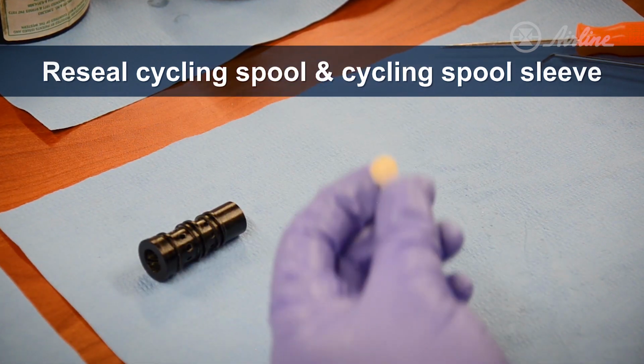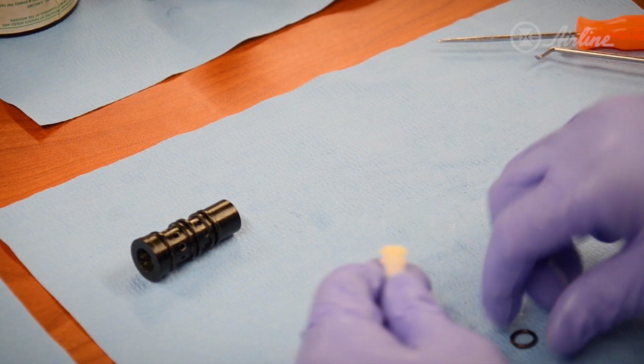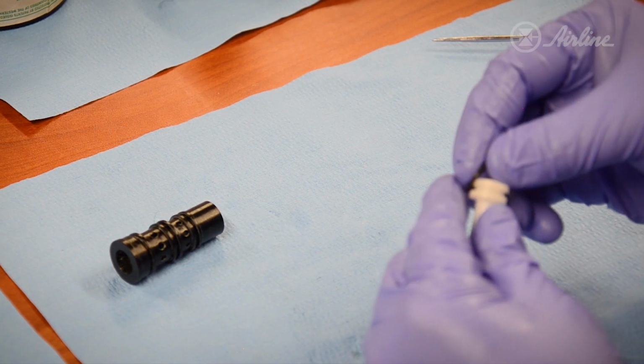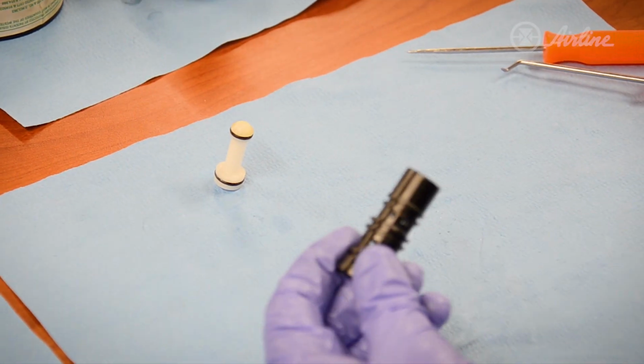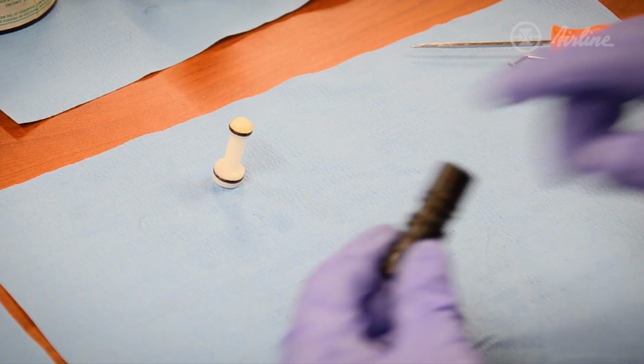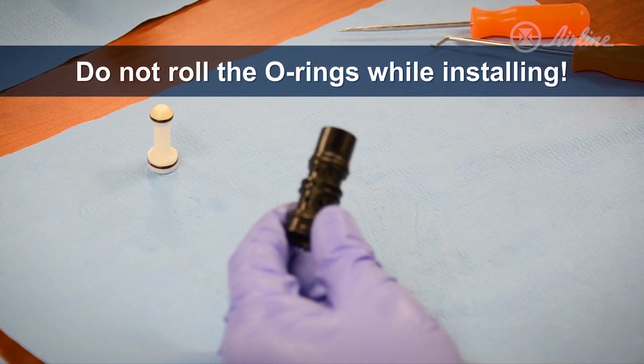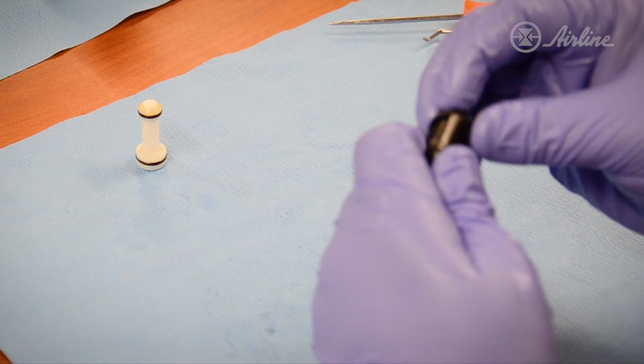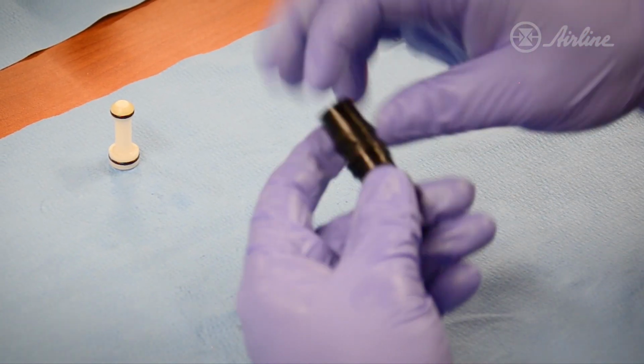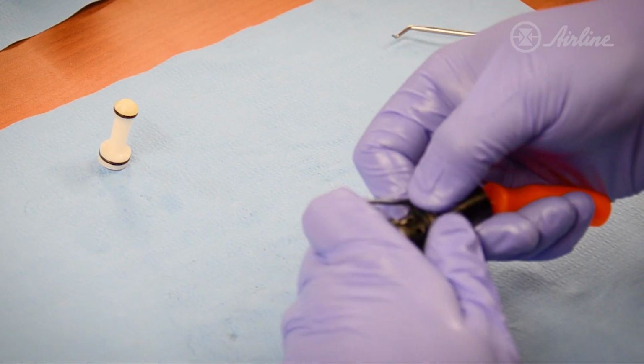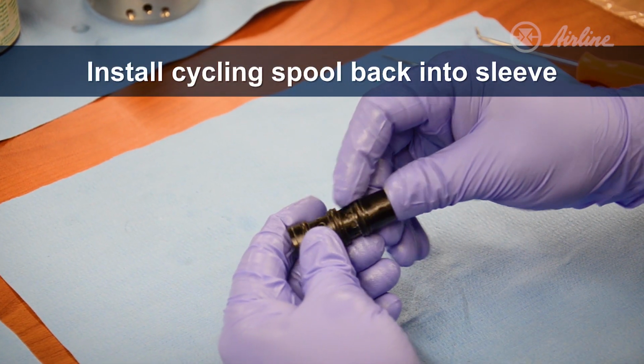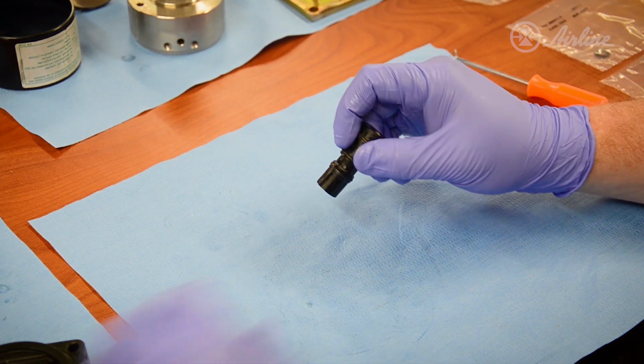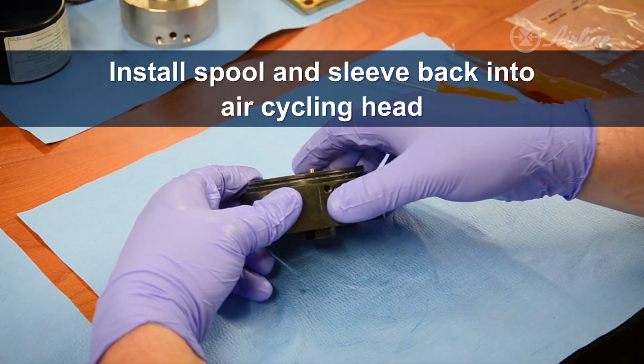Now we'll reinstall the O-ring seals back on the spool. And the other O-ring on the other side of the spool. And we'll also install the O-rings on the cycling sleeve. These can be tricky to get on, and you want to make sure that you don't roll the O-rings while installing them. If you roll the O-rings, they won't seal properly in the head. You can use a pick to help get these back where they need to go. Now we can install the cycling spool back into the sleeve. Once we have these 2 components resealed and lightly lubricated with the Haskel lubricant, they're installed back in to the air cycling head. And we can set that aside.